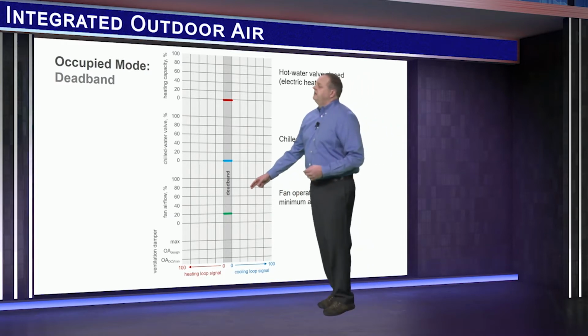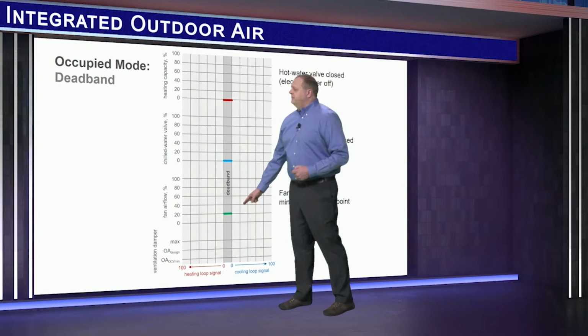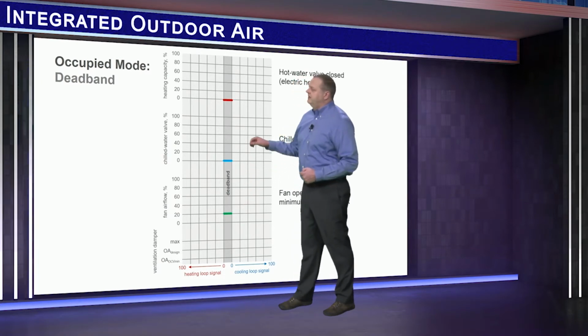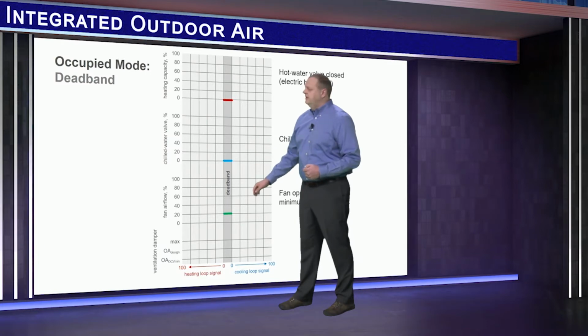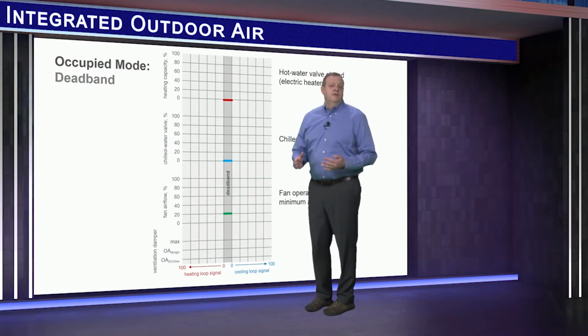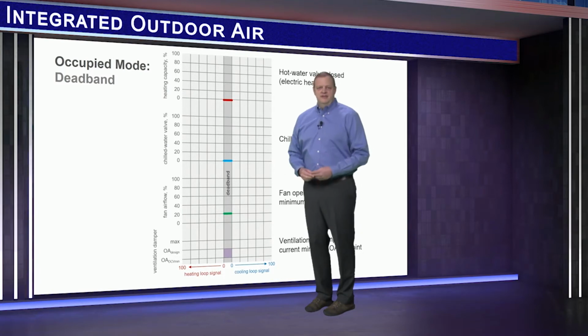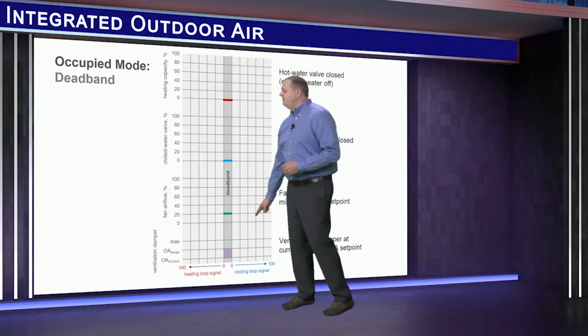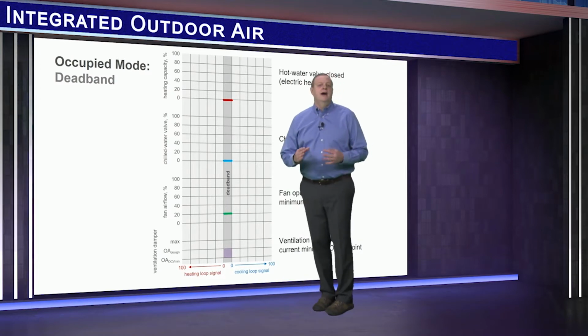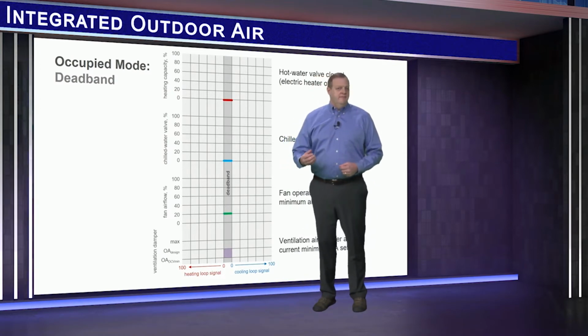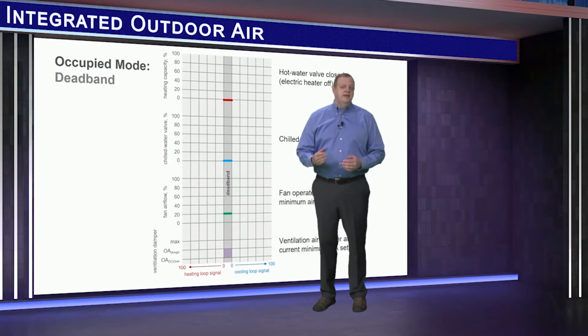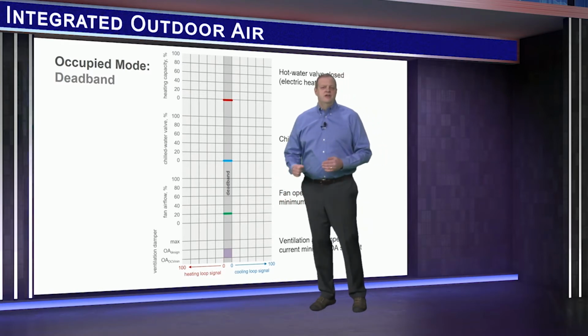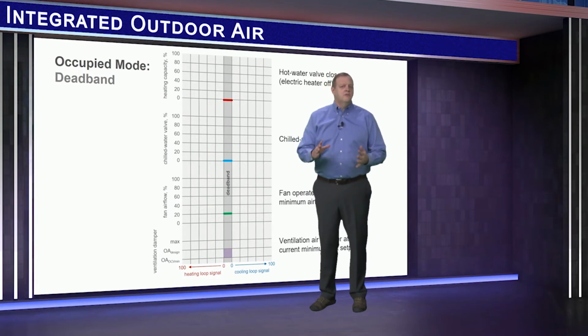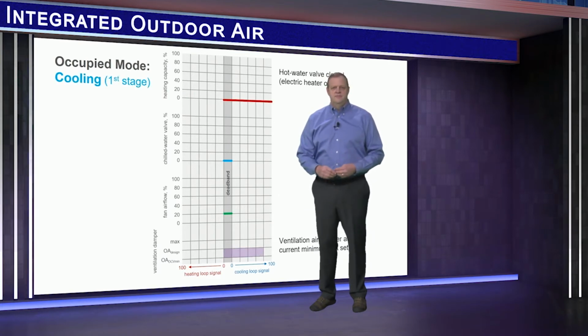In this dead band, the fan operates at its minimum airflow set point, with both the chilled water and hot water valves closed. Now I'm showing 20% minimum airflow as an example, but this is an adjustable setting. Meanwhile, the ventilation damper is controlled to the current minimum outdoor airflow set point. If demand-controlled ventilation is used, this will vary between the design outdoor airflow for the zone and some minimum airflow threshold. That's why I depict this as a range rather than as a single line. I'll talk more about demand-controlled ventilation in a few minutes.